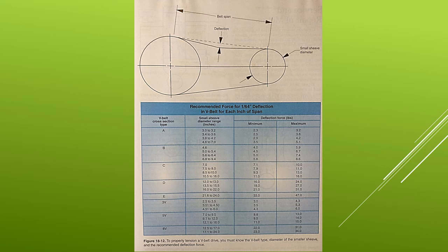To properly tension a V-belt drive, measure the length of the belt span as shown in figure 18-12. The force required to deflect the belt is 1/64 inch for each inch of span, which should be within the values shown in the table. There are tension gauges available that are designed specifically for tensioning V-belts. Follow the manufacturer's instructions that are packaged with the gauge.